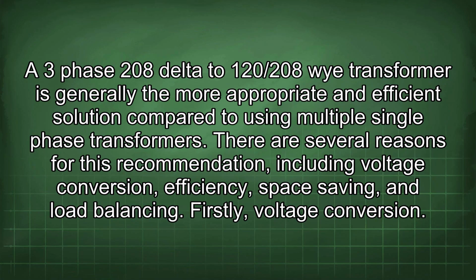Three-phase 208 delta to 120/208Y transformer is generally the more appropriate and efficient solution compared to using multiple single-phase transformers. There are several reasons for this recommendation, including voltage conversion, efficiency, space saving, and load balancing.